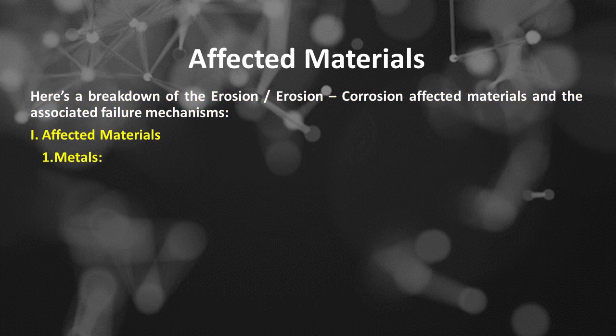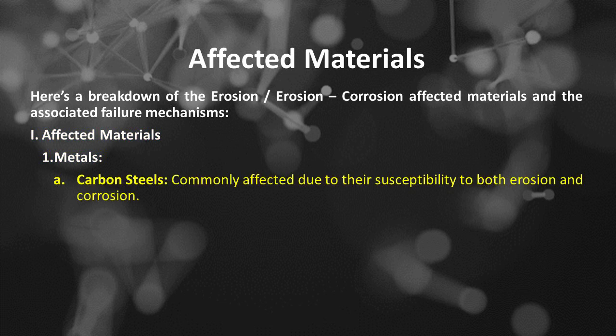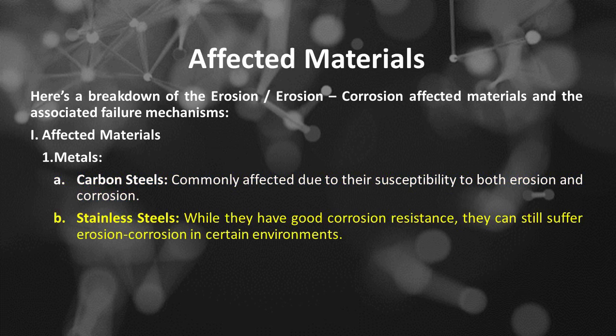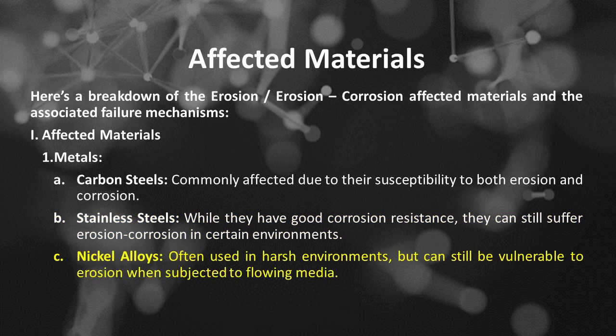From affected materials' point of view, we can break them down as follows. Number 1 is metals. The first of metal is carbon steels, commonly affected due to their susceptibility to both erosion and corrosion. The second of metal is stainless steels. While they have good corrosion resistance, they can still suffer erosion-corrosion in certain environments. The third of metal is nickel alloys, often used in harsh environments, but can still be vulnerable to erosion when subjected to flowing media.